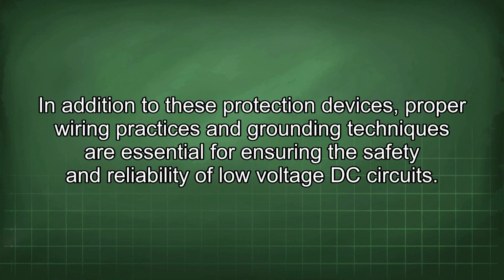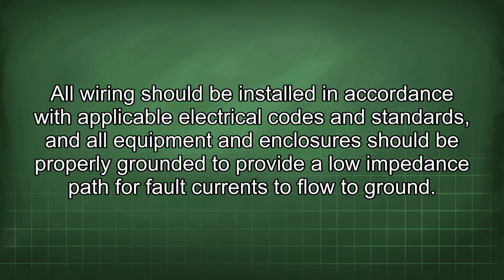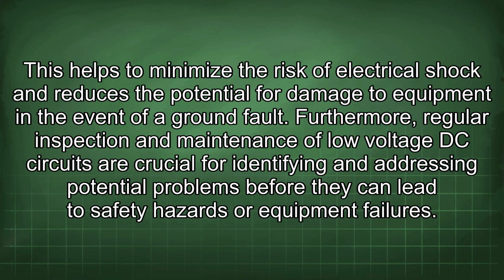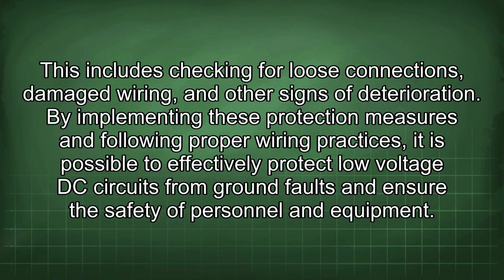In addition to these protection devices, proper wiring practices and grounding techniques are essential for ensuring the safety and reliability of low-voltage DC circuits. All wiring should be installed in accordance with applicable electrical codes and standards, and all equipment and enclosures should be properly grounded to provide a low impedance path for fault currents to flow to ground. This helps to minimize the risk of electrical shock and reduces the potential for damage to equipment in the event of a ground fault. Furthermore, regular inspection and maintenance of low-voltage DC circuits are crucial for identifying and addressing potential problems before they can lead to safety hazards or equipment failures. This includes checking for loose connections, damaged wiring, and other signs of deterioration. By implementing these protection measures and following proper wiring practices, it is possible to effectively protect low-voltage DC circuits from ground faults and ensure the safety of personnel and equipment.